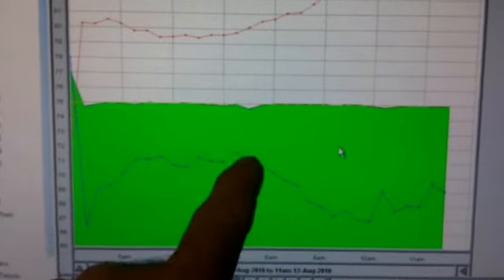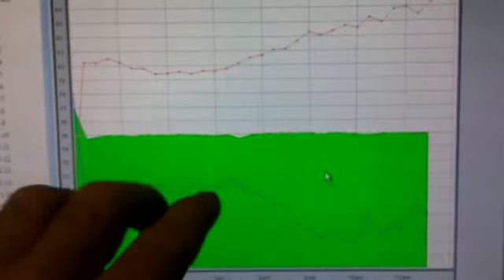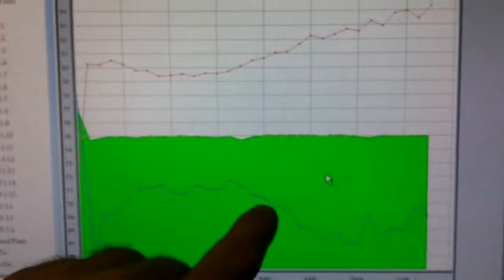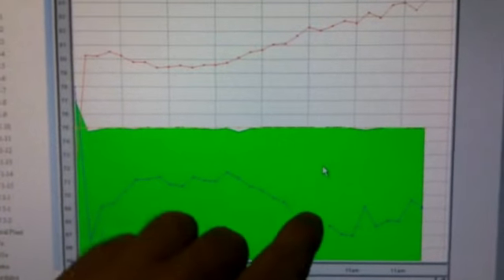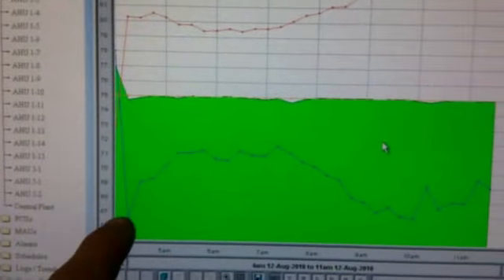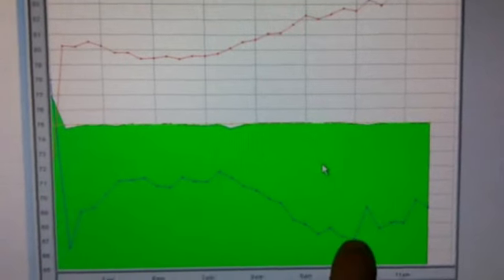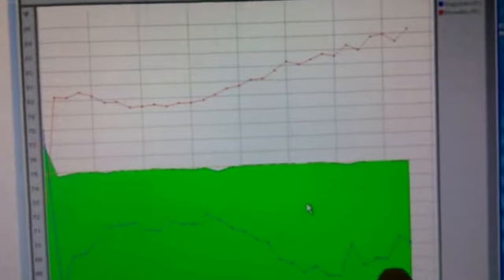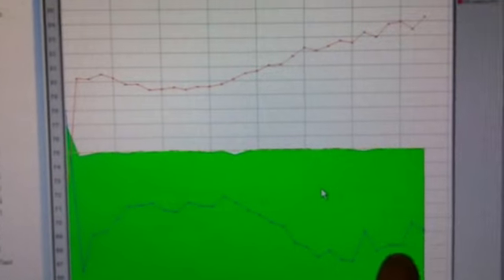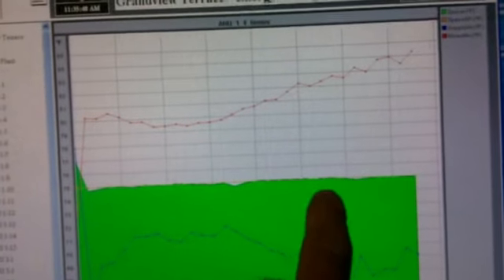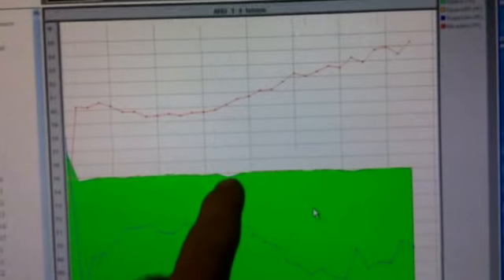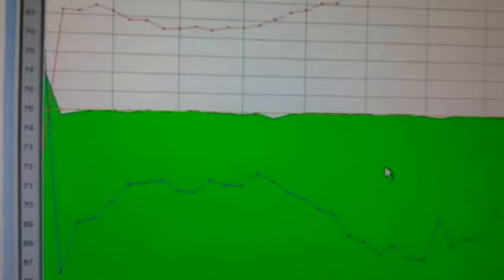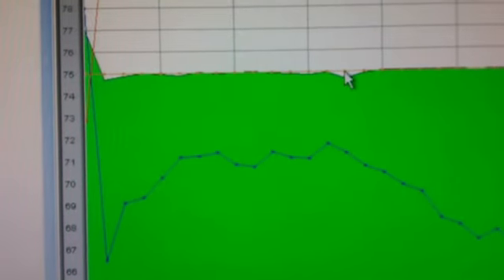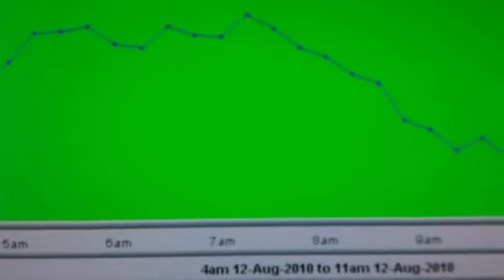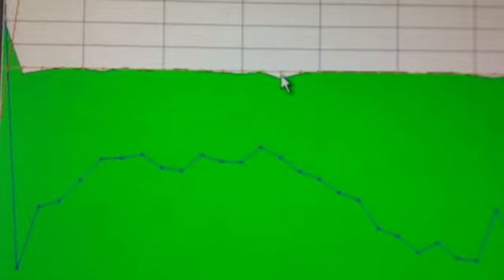So with the heat load in the room, plus the increase in outside temperature driving up the mixed air, you'll see that the output of the supply air has lowered the temperature. See, putting out the 66 degree air right now, like 68, to maintain a steady room temperature. See, that's pretty good. It has a little dip right there. But I mean, that's only a couple tenths of a degree, because there's 75 degrees, and that pointer there is 74.7. That's only 3/10 of a degree that we're fluctuating in that room.